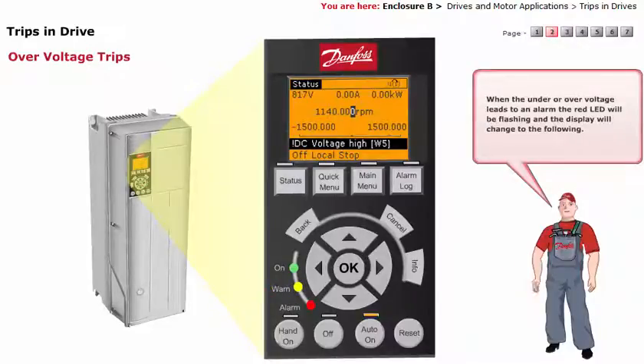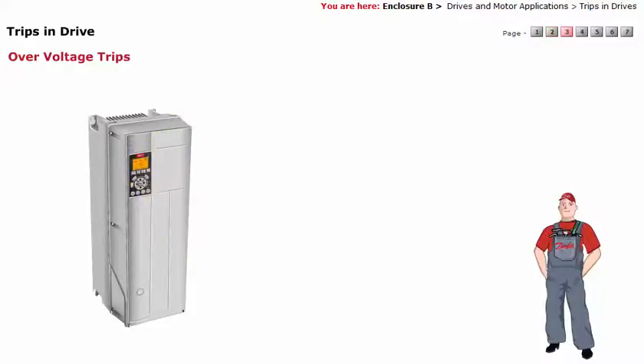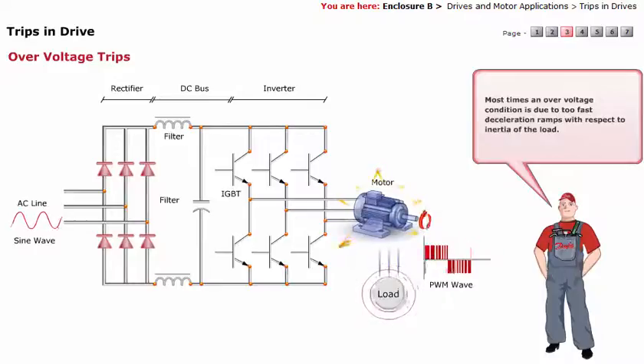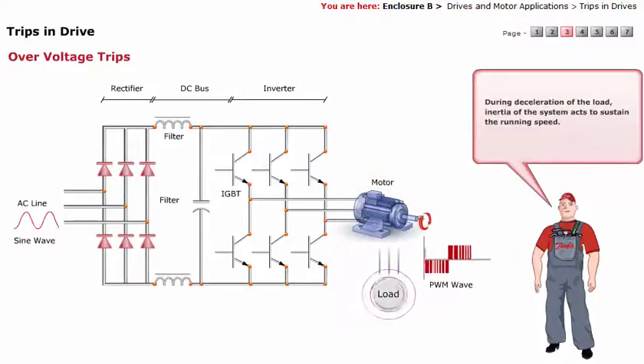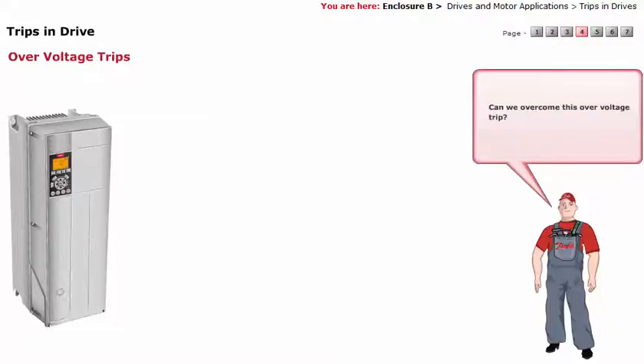When under or over voltage leads to an alarm, the red LED will be flashing and the display will change accordingly. Most times, an over voltage condition is due to too fast deceleration ramps with respect to the inertia of the load. During deceleration, the inertia of the system acts to sustain the running speed. Can we overcome this over voltage trip?